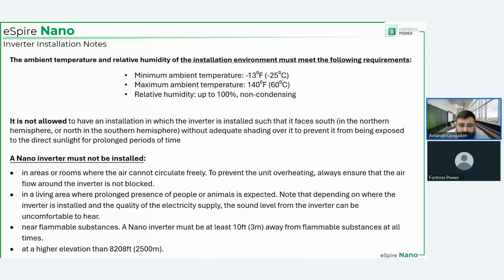Granted, amazing, very functional, quality made, all of that, but still, it's an air-cooled inverter, and ambient temperature will have an effect on it. So the minimum ambient temperature to which it should be exposed is minus 25 degrees C or minus 13 degrees Fahrenheit. Maximum ambient temperature should be 140 degrees Fahrenheit. Relative humidity, this is very common in our industry, up to 100% non-condensing.